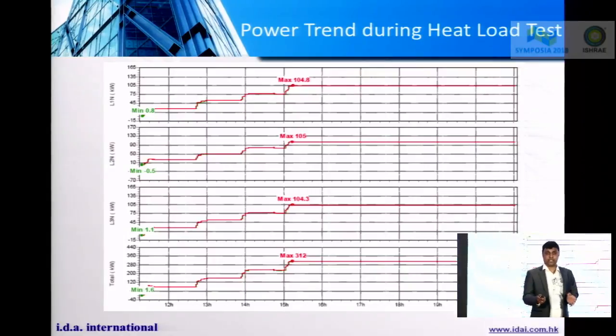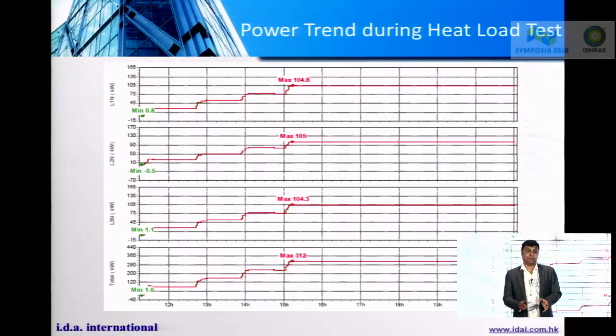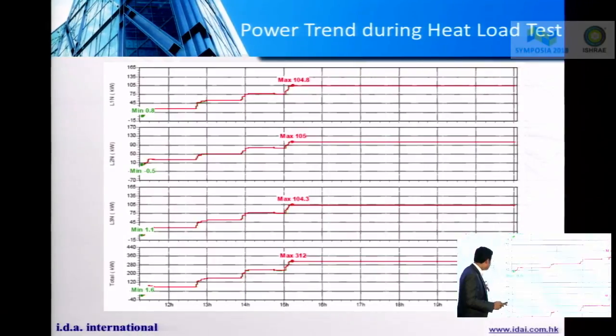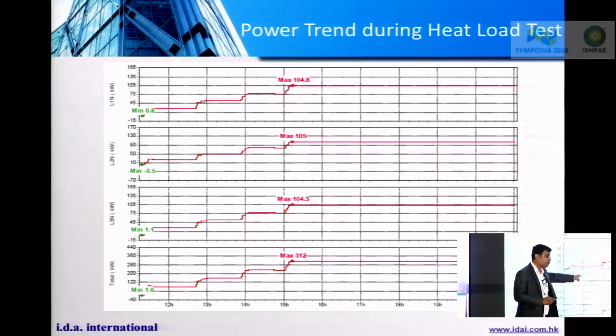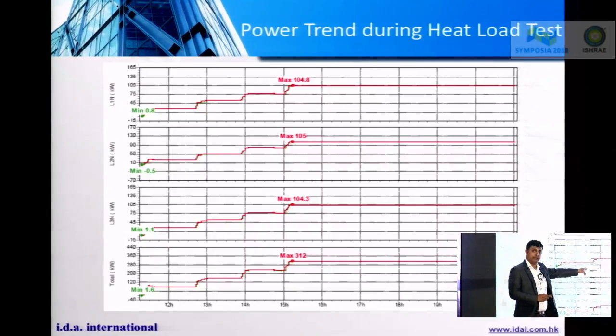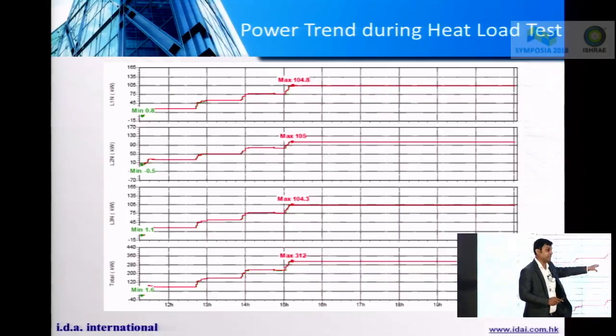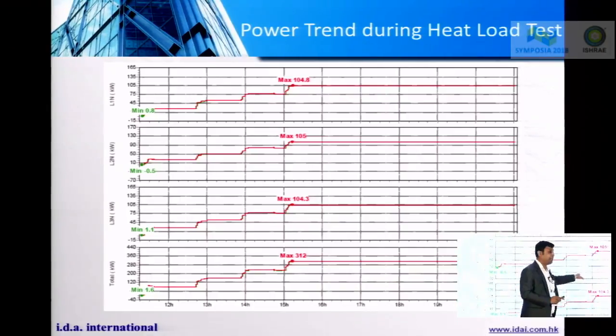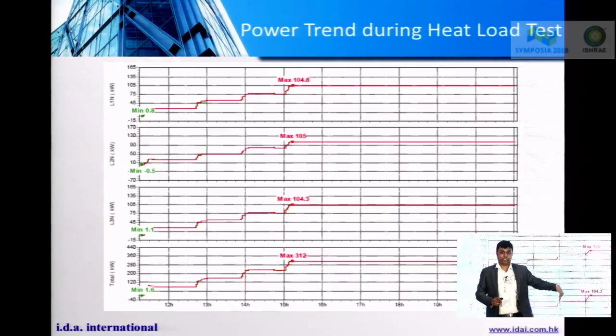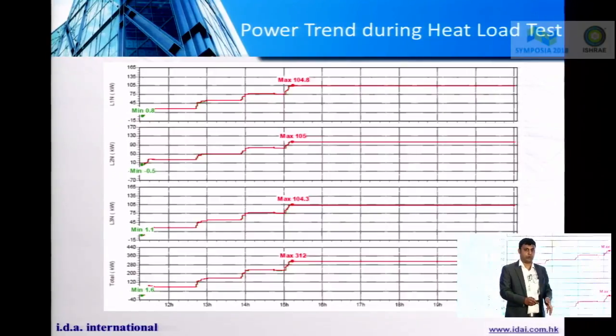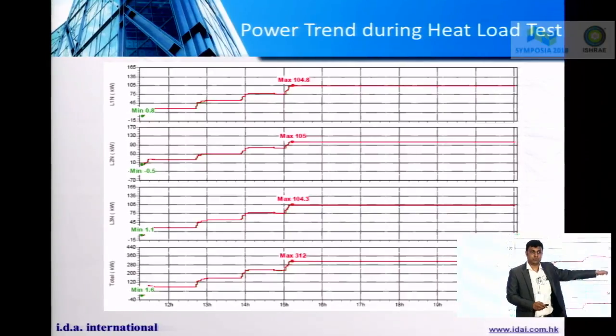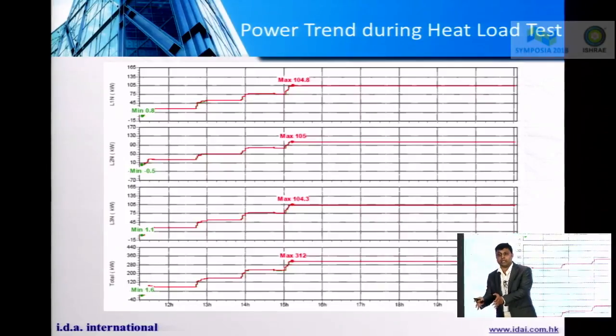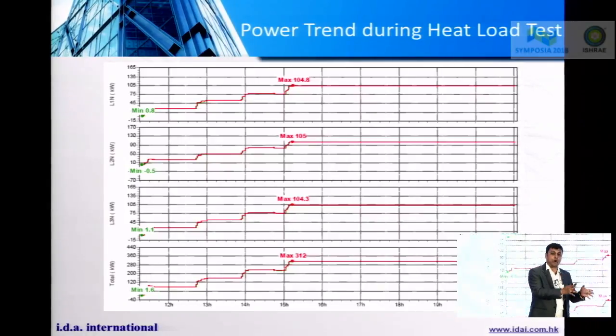During the heat load test, you have to very closely monitor the power. Like I started with 25%, then I jumped to 50%, then 75%, and then 100%. And throughout the heat load test, the power was intact. There was no dip, no drop of load. It was a smooth line. So when you're verifying the thermal conditions, at the same time it is important to verify the power. Okay, we cannot neglect that.